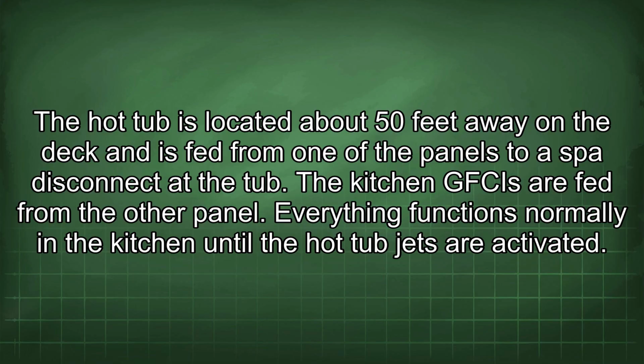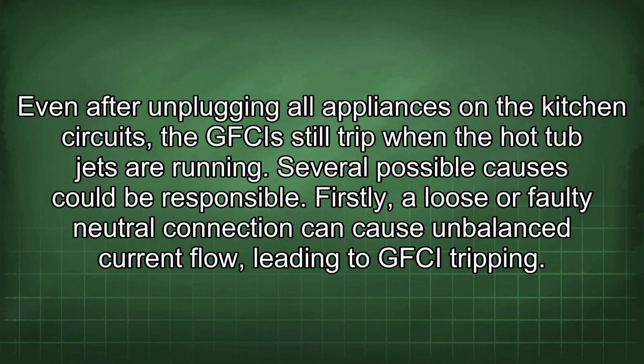The kitchen GFCIs are fed from the other panel. Everything functions normally in the kitchen until the hot tub jets are activated. Even after unplugging all appliances on the kitchen circuits, the GFCIs still trip when the hot tub jets are running. Several possible causes could be responsible.